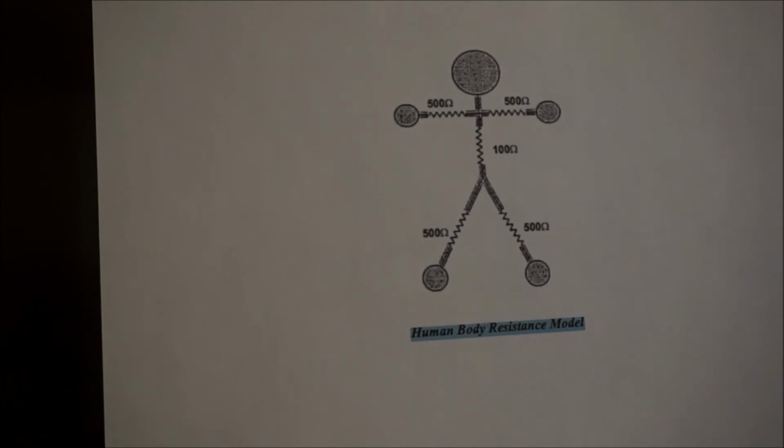The general rule on skin, usually on most things that I've heard and read, is 10,000 ohms. So if you wanted to say that your skin has the maximum amount of resistance that it could have, or the average amount, I guess, at 10,000, you're still looking at 40 milliamps possibly going through your body at this stage. So yeah, you're working on amps with 400 volts in it.